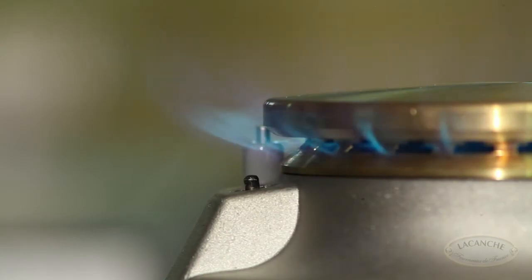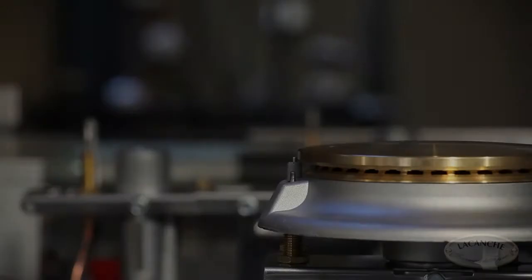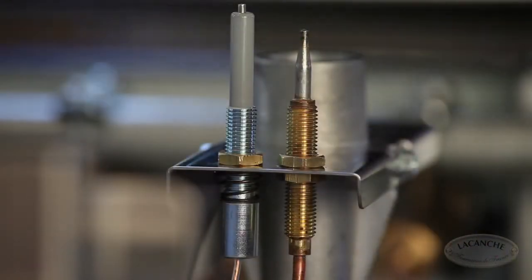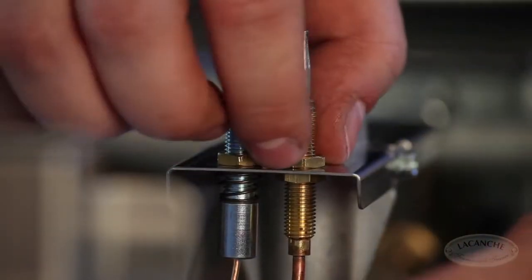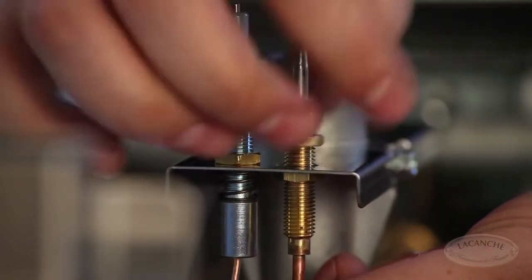If the probe is adjusted too low, the valve will not stay open and the burner will go out. Adjust the height of the probe by manipulating the position of the backing nut on the threaded shaft.